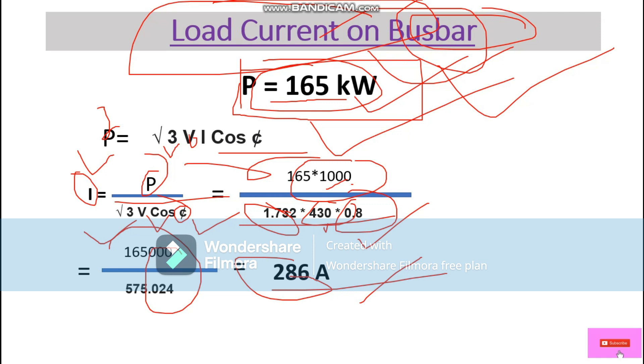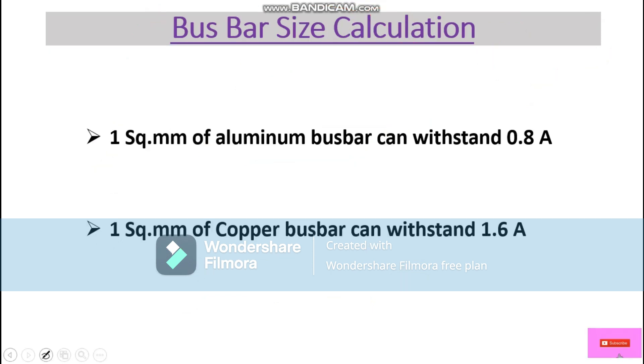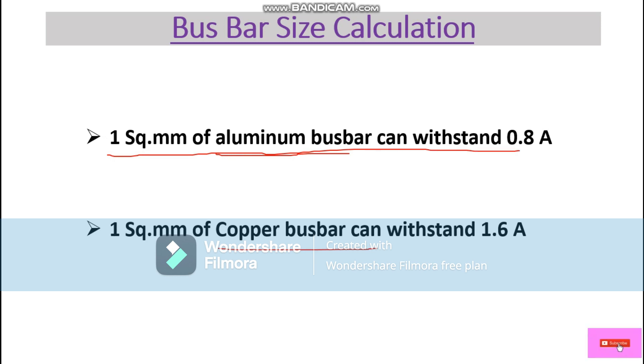Now according to this load current we calculate the bus bar size. The thumb rule is: one square mm of aluminium bus bar can withstand 0.8 ampere, and one square mm of copper bus bar can withstand 1.6 ampere. We will now calculate the copper bus bar size.